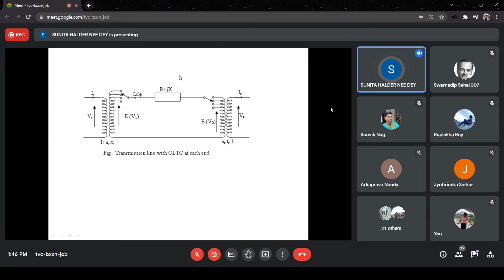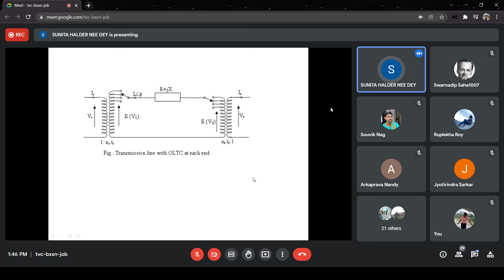Then due to MMF balance at the receiving end, the current in the primary side is I into NRTR, and in the secondary side it is IR. So I into NRTR equals IR. So from there we are getting an expression of I. Why is it required? Because the voltage drop is in terms of I, because IR is not directly related to the voltage drop of the line, but I is related. But we need the expression of voltage drop in terms of IR, then we can relate it with the taps, right? For that reason, I can be converted to IR in terms of IR and NRTR. So just put it there, right?